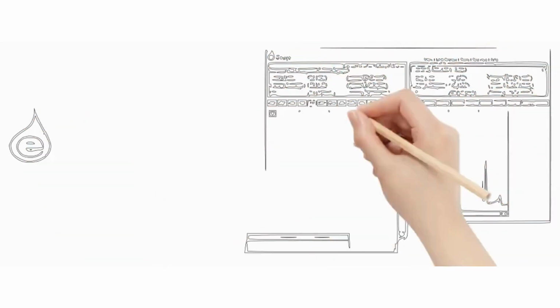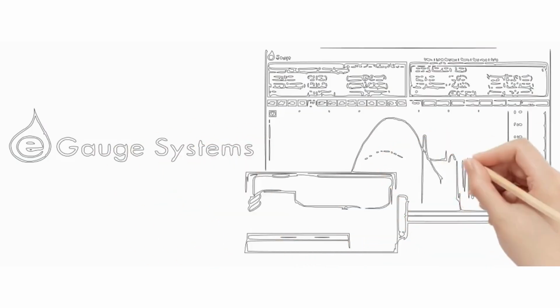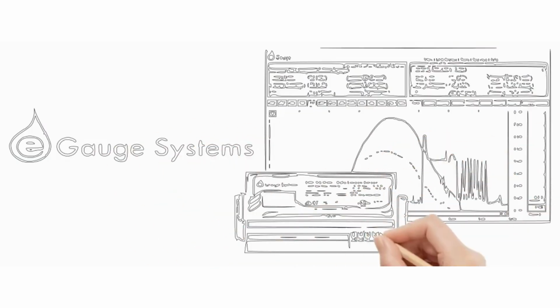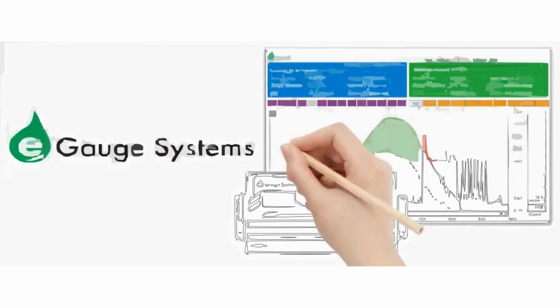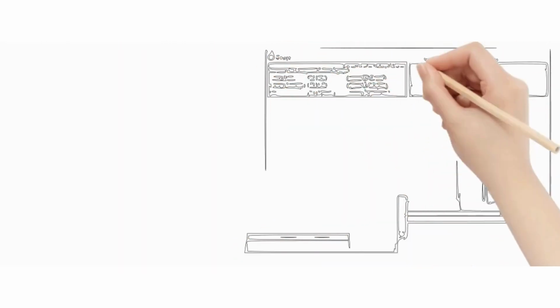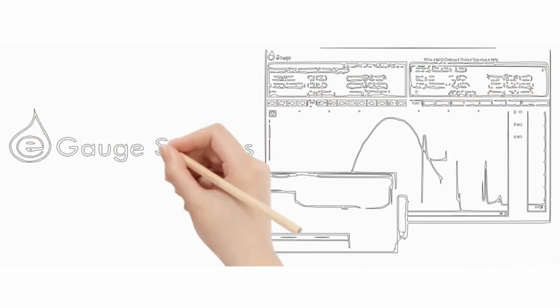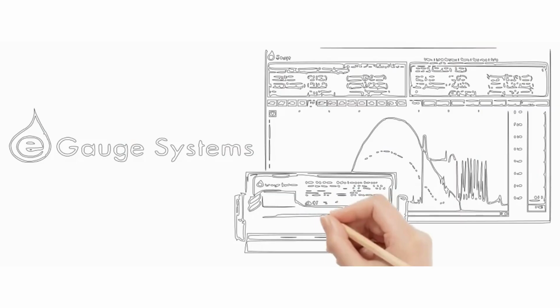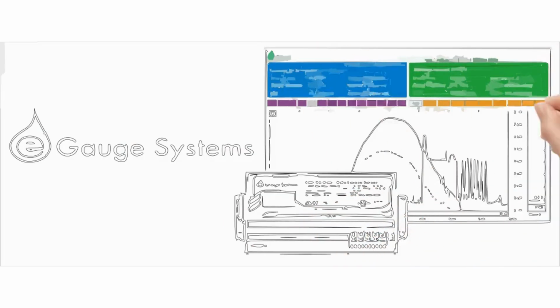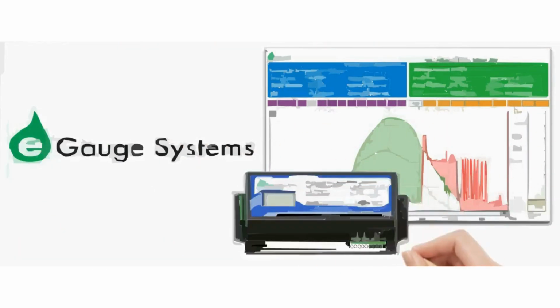So that synchronization is key, it gives you a perfect snapshot across everything at the exact same millisecond. It guarantees phase accuracy, and you need that to calculate real power, the actual usable energy you're consuming and paying for. So you've got this super clean, synchronized high-res data, thanks to the ADCs and simultaneous sampling.